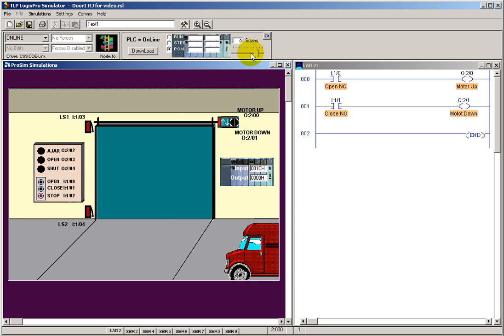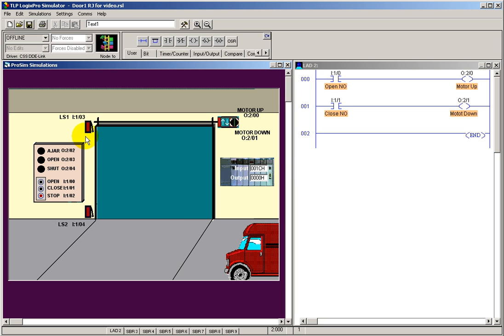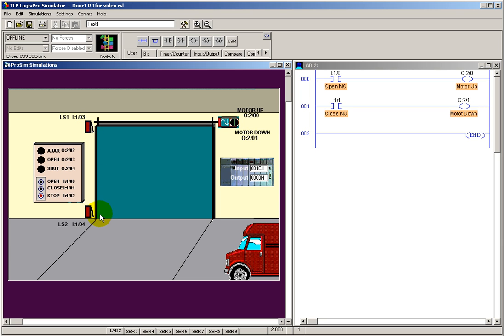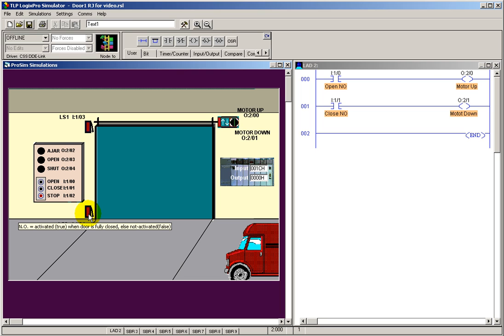So let's go back to programming mode and put a couple of instructions in here to prevent that using the limit switches. Let's look at our limit switches here. The upper limit switch is going to be treated differently than the lower limit switch, and that's just because of the application. Even though they're identical switches, they are normally open. If you roll over them, it actually says normally open, activated, true when door is fully closed. Else, not activated or false. That's a little confusing.